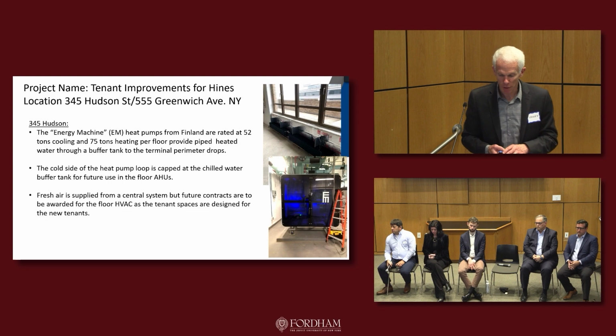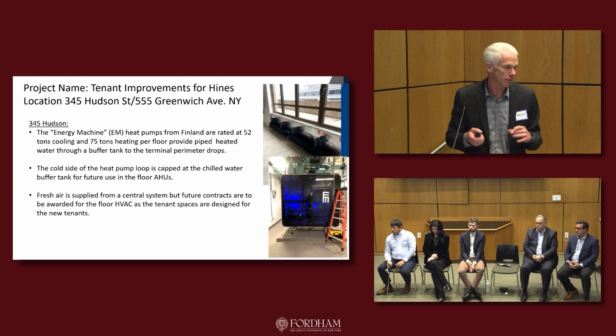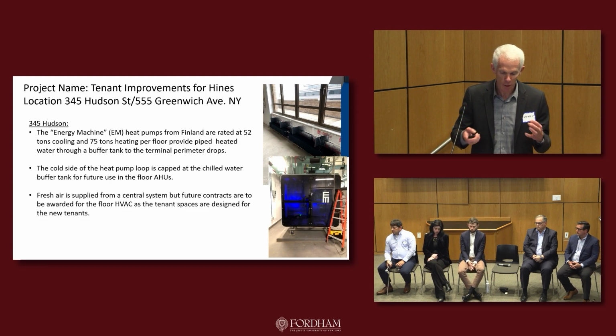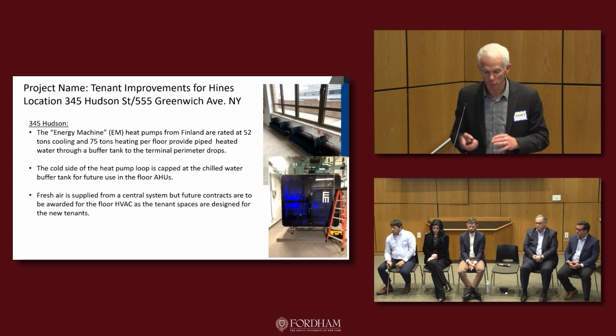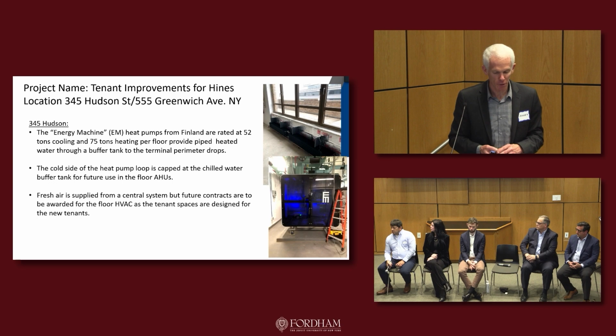The cold side of the heat pump loop is capped at chilled water, creating a buffer tank when it's in heating mode for future use on the air handling units that will be installed. Fresh air supply has to come from a central system as the tentative spaces are leased out.